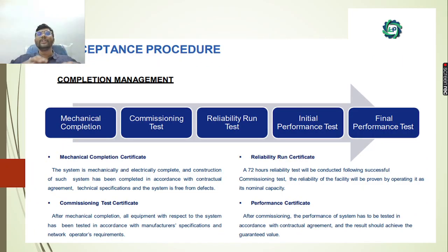Then, for completion management in the acceptance procedure, we need to do the mechanical completion, commissioning test, reliability run test, initial performance test, and final performance test. When you're going for mechanical completion, the system should be complete mechanically and electrically, and the construction of the system should be completed in accordance with the contractual agreements and technical specification. Next is the commissioning test certification. After mechanical completion, all the equipments of the system need to be tested in accordance with the manufacturer's specifications and the network operator's requirements.